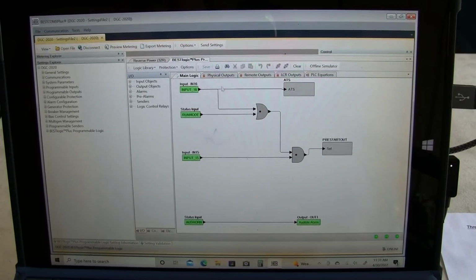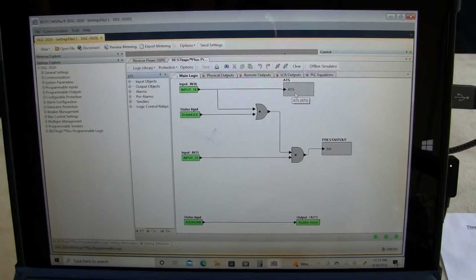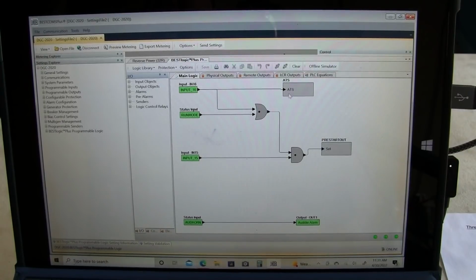Our input 16 triggers the ATS function of the controller. That pretty much is the remote start input. So when input 16 is pulled to ground, the genset starts up and runs. When we shift the genset into run mode, well, it would obviously run. We don't typically need this status input here, but I do need it for the pre-start function. And then there's input 15, and then we got one contact output or status input.